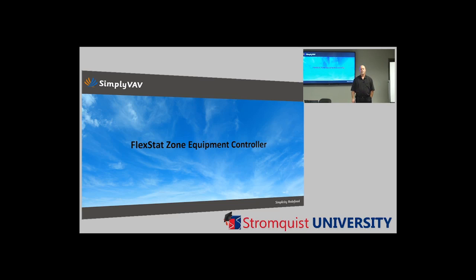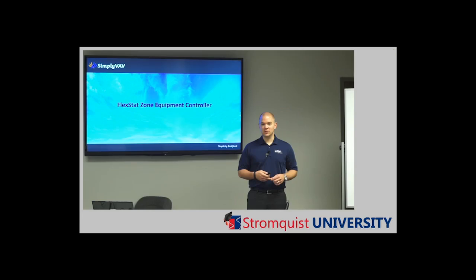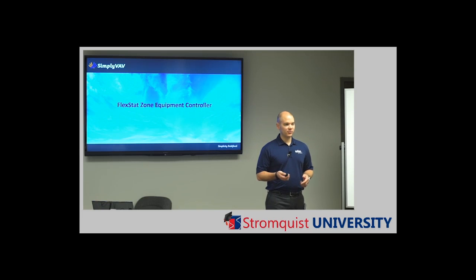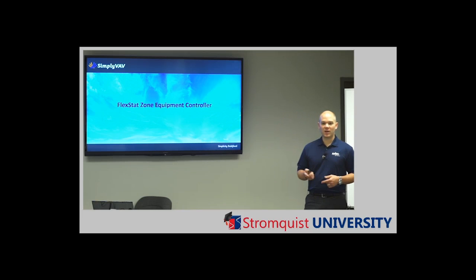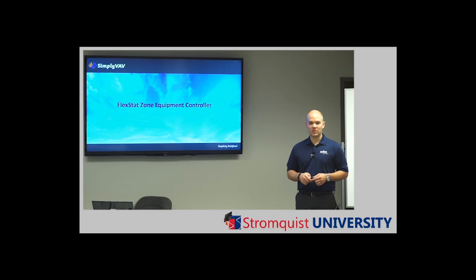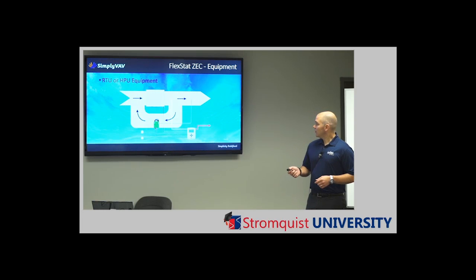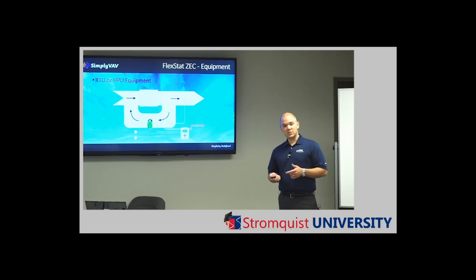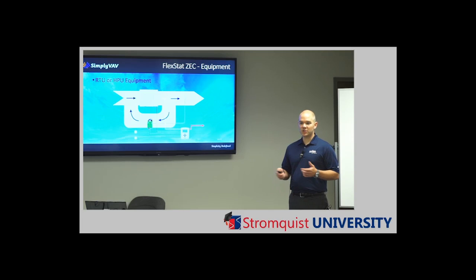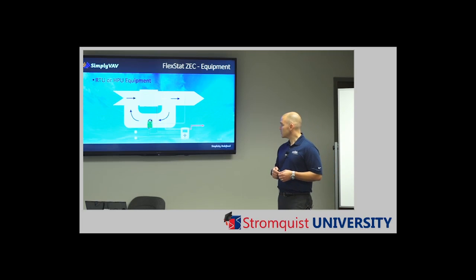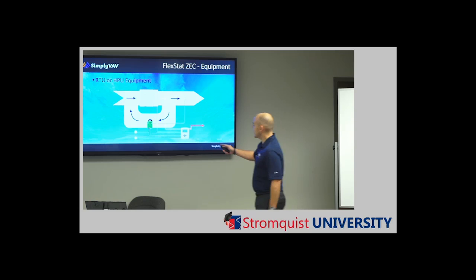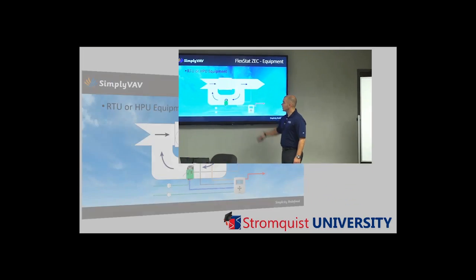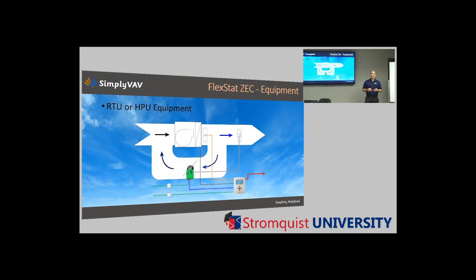Now we'll flip over and let Mr. Erich. I'm Erich Kreuter, KMC Controls. I'm a hardware product manager. I'm going to talk to you a little bit about the FlexStat zoning equipment controller that is a companion product to our Simply VAV product line. So for zoning applications where you have multiple zones, pressure independent systems, we can install a FlexStat on the rooftop or the heat pump to stage up or stage down that DAT to deliver heating or cooling as necessary to the zones.